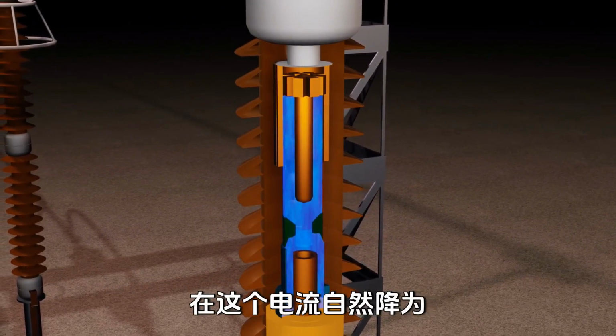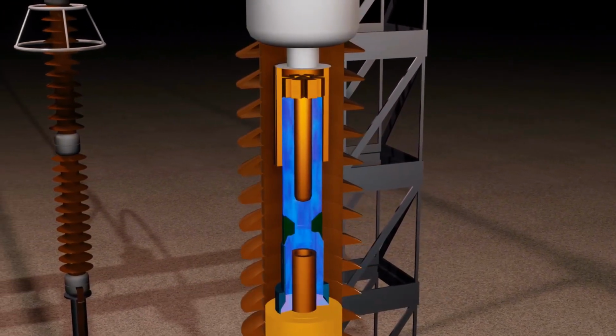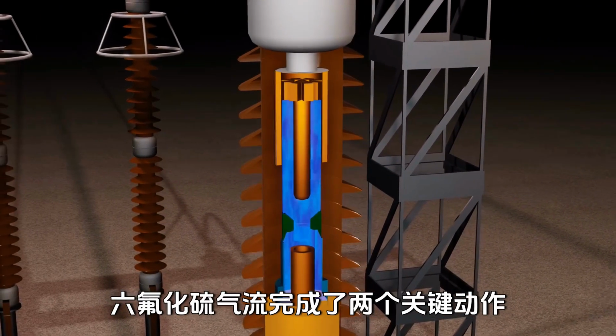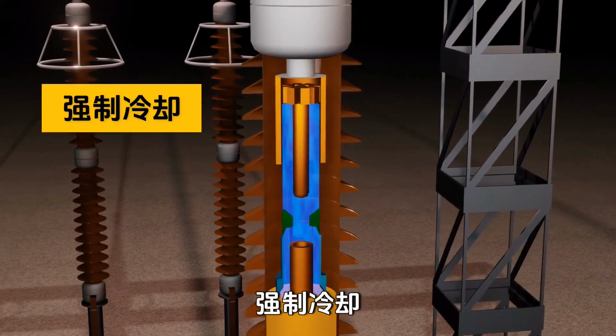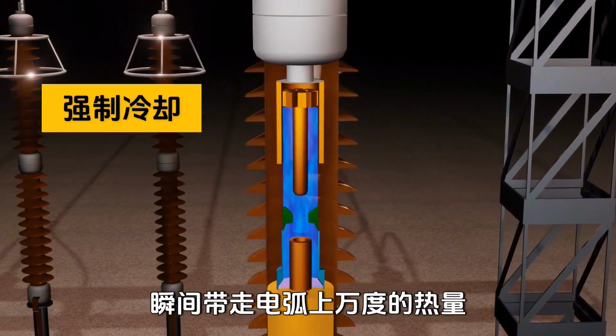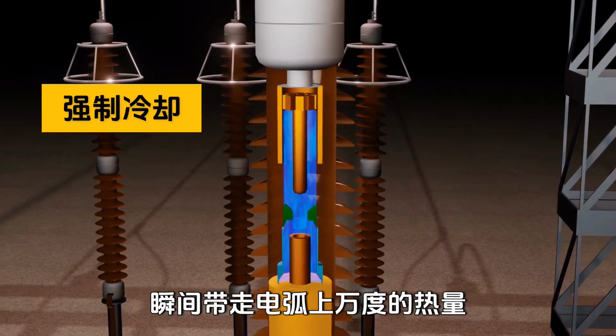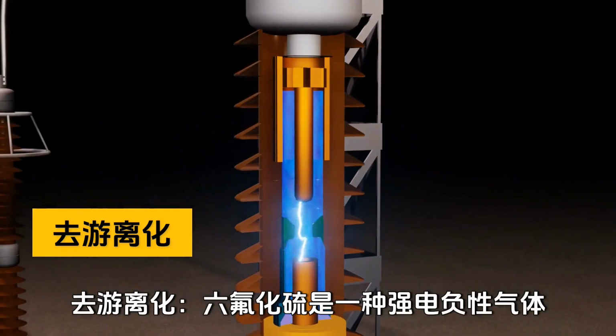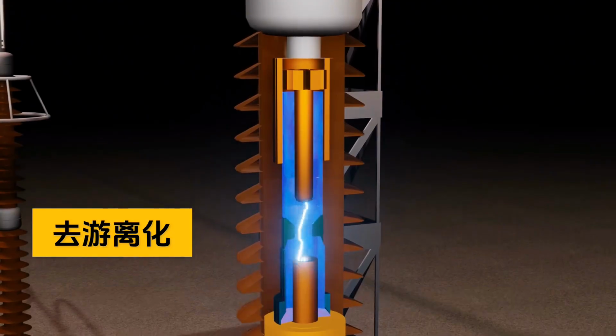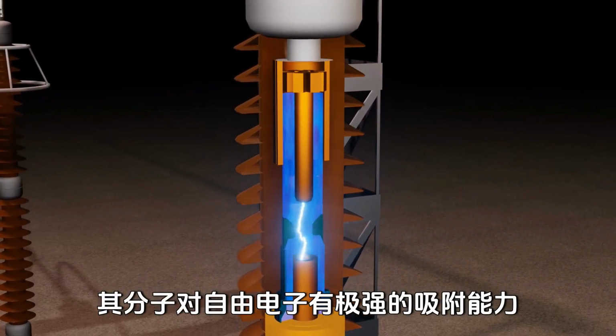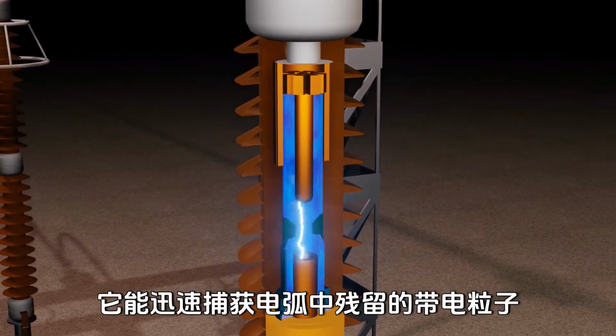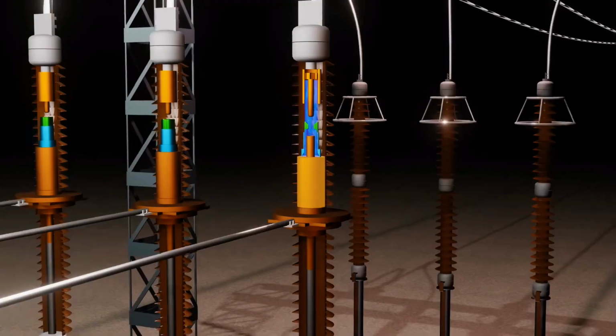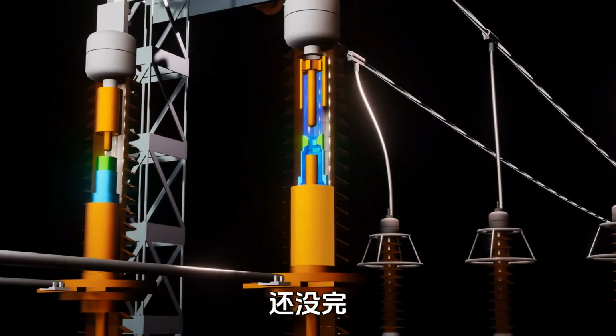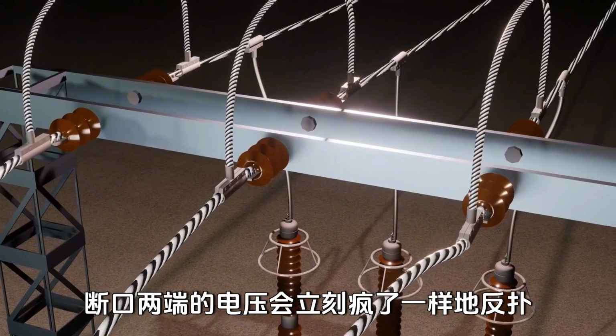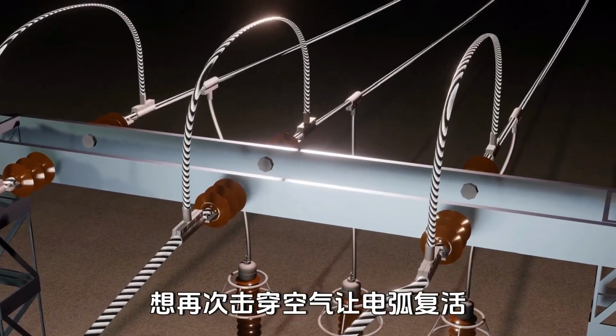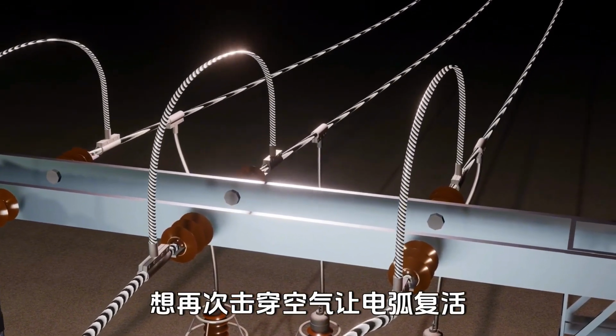First, supersonic gas flow instantly removes the extreme heat from the electric spark, cooling it down in microseconds. Second, it performs deionization. Because SF6 is a highly electronegative gas, its molecules quickly capture the free electrons left in the spark. But even after the spark is gone, the job isn't over. A sudden voltage surge appears across the circuit gap, trying to break the air again and reignite the spark. This is called transient recovery voltage.